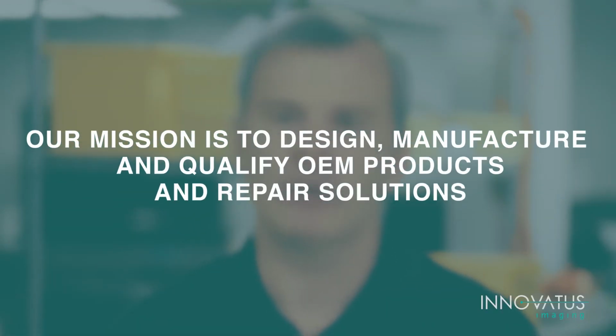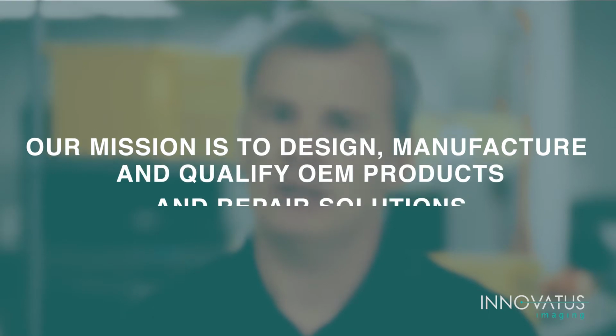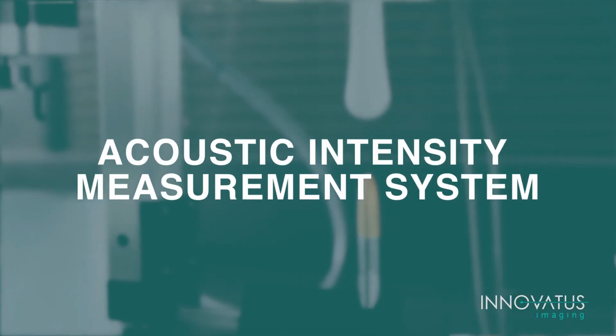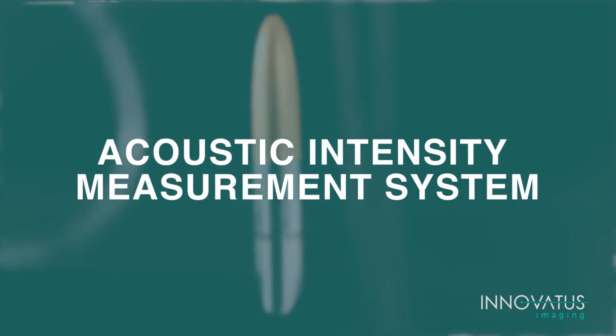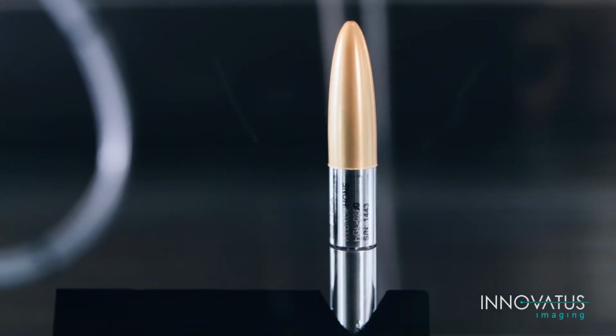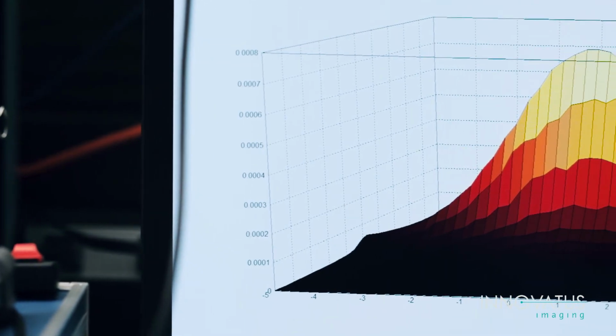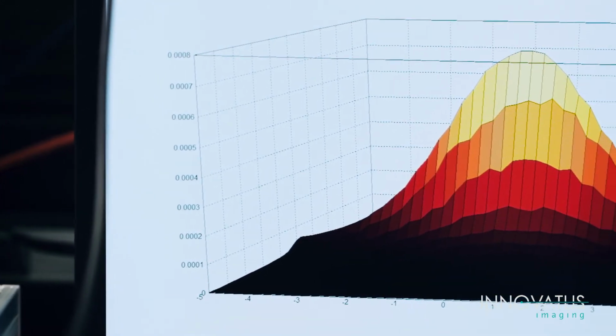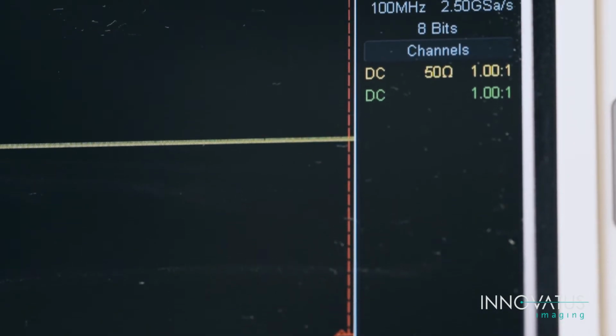So as we walk through our technical journey, we have several pieces of equipment and tools that are critical to our job, whether that job is designing, manufacturing, qualifying OEM products, or qualifying a repair solution. So we'll start with acoustic power measurement. We have two primary pieces of equipment we use here. The first is a hydrophone tank. This allows us to three-dimensionally map the acoustic pressure field that comes from a transducer, and this can be used to derive key safety factors, mechanical index and thermal index, that are used to ensure our products are safe.